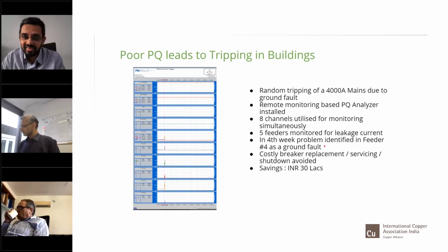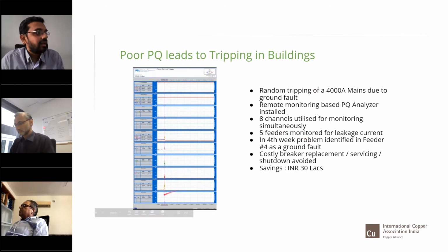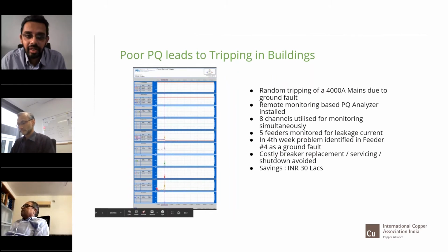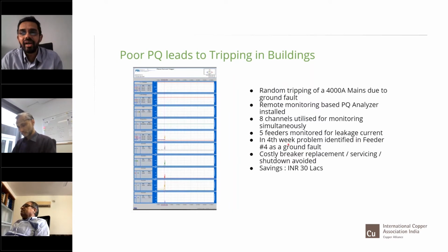It took us 4 weeks to find out, and it captured a sudden rise in the zero sequence current at one of the feeder breakers, which allowed us to identify that there was a ground fault at that breaker. It avoided a costly breaker replacement, because the facility was contemplating replacing the breaker rather than knowing the cause of the tripping of the breaker due to ground fault.